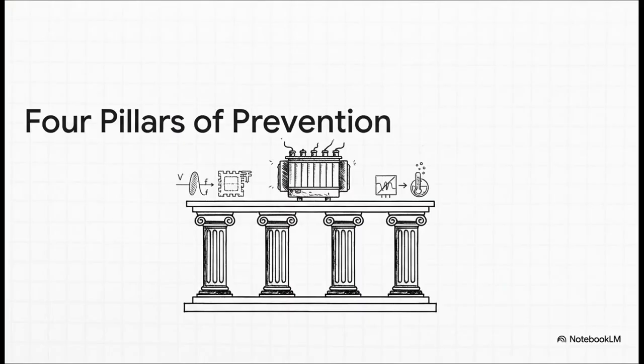And it really boils down to these 4 pillars. First, you have to strictly respect the voltage to frequency, or V per hertz, limits during operation. No exceptions. Second, it's about designing the transformer right from day one, choosing the right core material and sizing it with a healthy safety margin. Third, you have to actively manage things like DC bias and those big inrush currents. And finally, you monitor its health constantly, looking at things like temperature and dissolved gas in the oil to catch any signs of stress long before they become a problem.